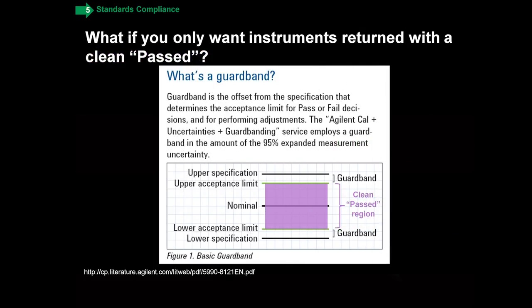Some of our more demanding customers say, 'when it's sent back to me I don't want to see any of those F double daggers or the U for uncertain.' We understand that, and that's really what a guard band is all about. A guard band is simply the offset from the specification that determines the acceptance limit for pass or fail decisions and where we perform adjustments.